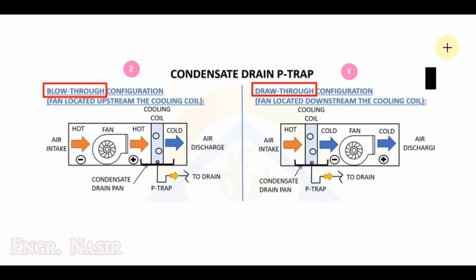Now we come to the main topic — calculation of trap size for condensate drain piping for AHU and FCU. Before starting the calculation, we need to understand the configuration of AC units. These units can be divided into two types: draw-through type and blow-through type. In draw-through type the cooling coil is before the fan, while in blow-through type the cooling coil is after the fan. In common use, only the draw-through type is typical.